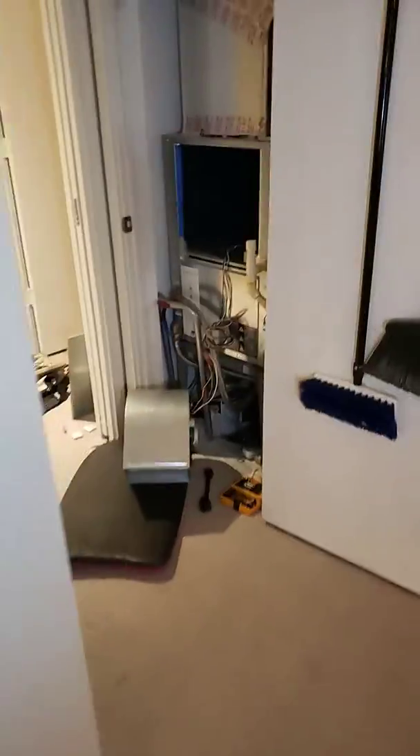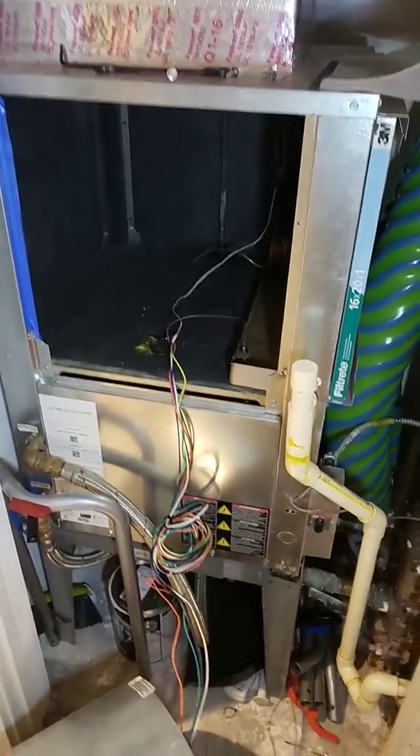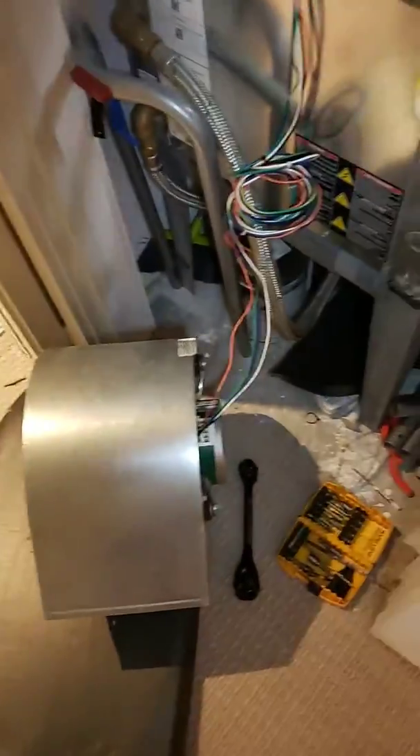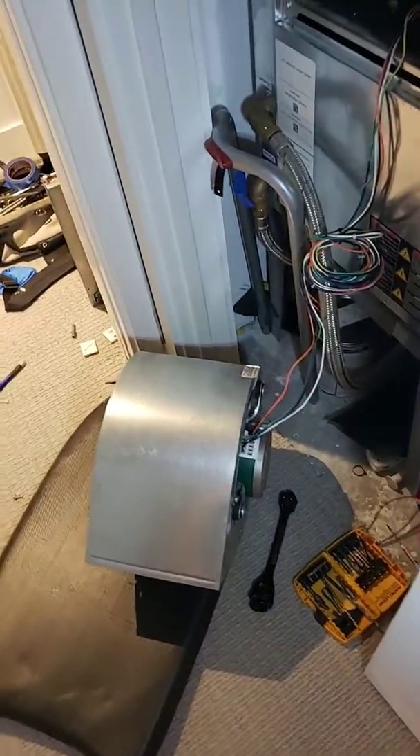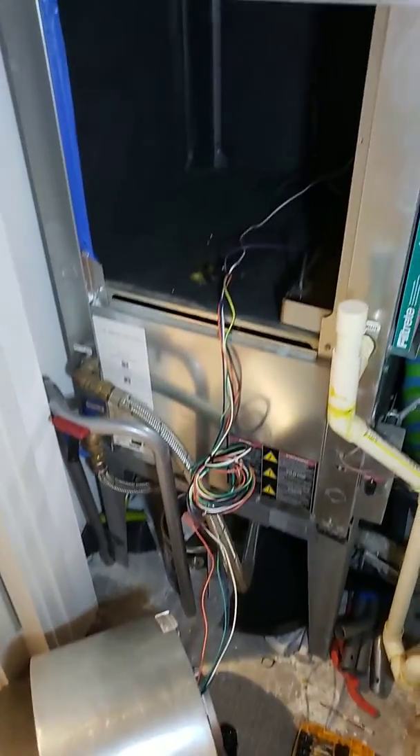This building is only two years old and I've got a Bosch heat pump. I noticed the past few months that this fan motor never shut off — it just would keep running. It would cool the unit down perfectly, but it just would never shut off.